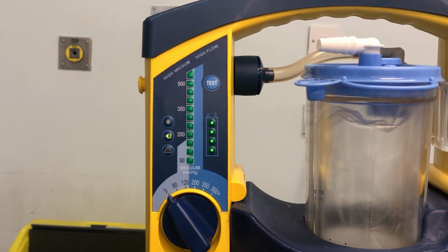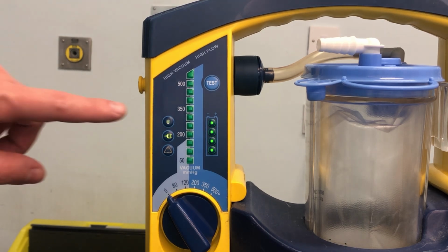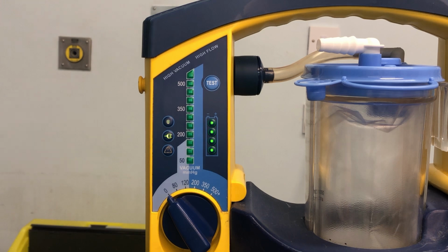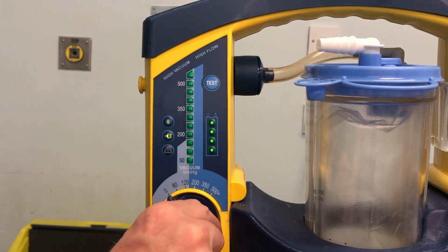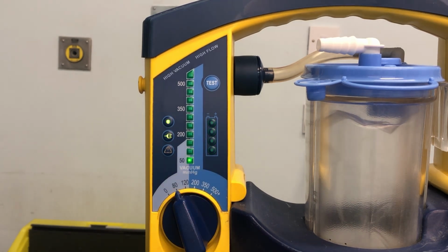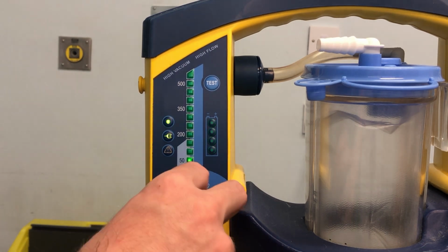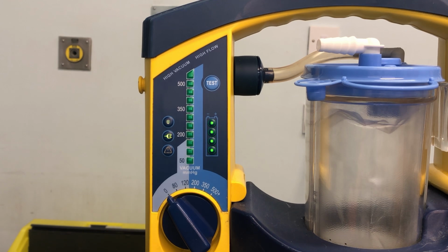So you have a power on indicator. It's a green LED and it has 3 modes. It is lit continuously while the LSU is switched on. It flashes rapidly, approximately twice per second, during a device test, and it flashes slowly, approximately once per second, while the automatic power save function is activated if the device test is interrupted or if the battery is discharged.